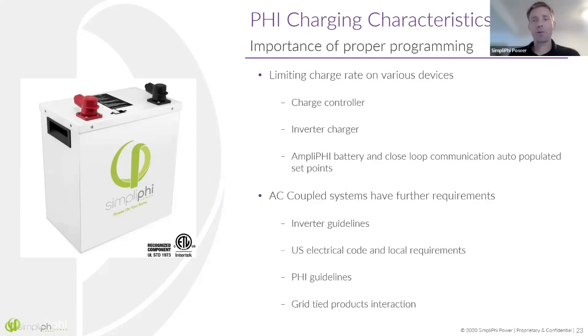If you have an AmpliPHI battery with proper equipment that has closed loop communications, like a Sol-Ark or our inverter, the battery can communicate the rate at which it wants to be charged, and it will auto-populate those settings with the appropriate programming. AC coupled systems have further requirements for setting charging parameters, because typically they're either charging at full rate or not charging at all. So make sure to size your battery bank with enough batteries to handle the full charging from your AC coupled system.